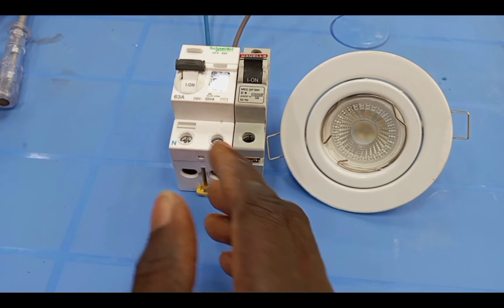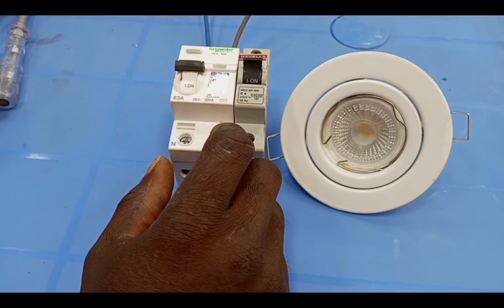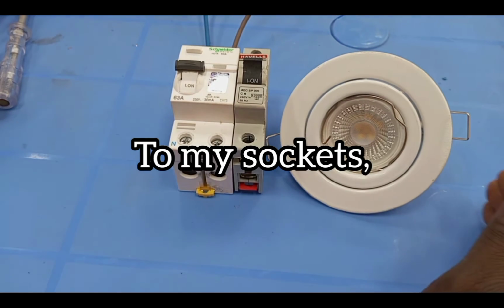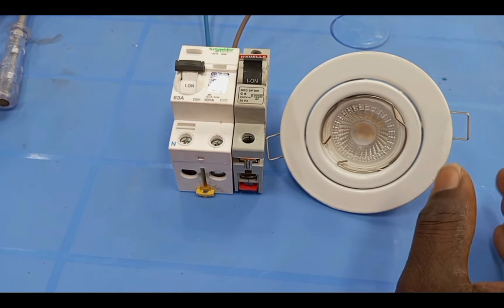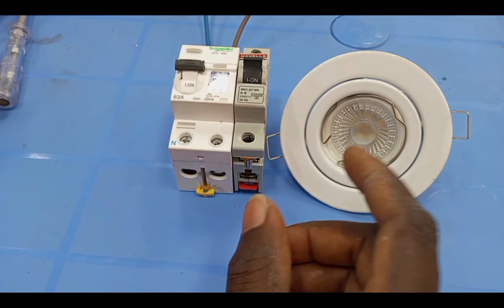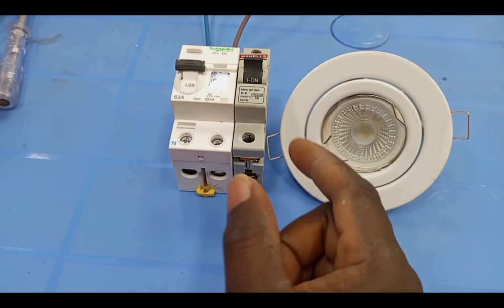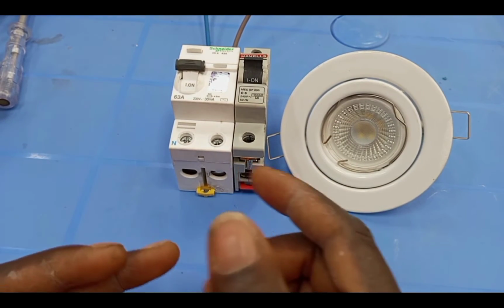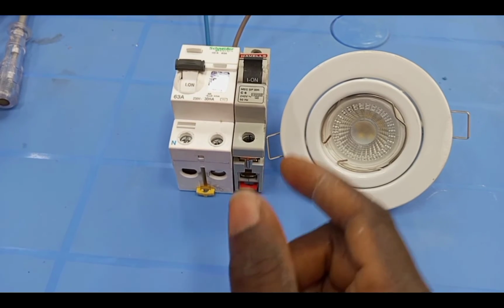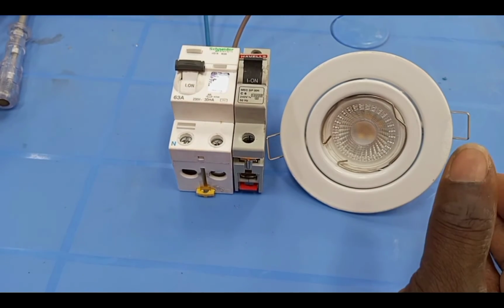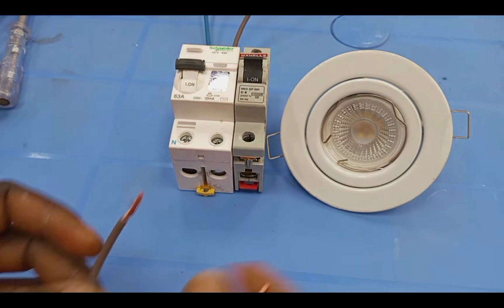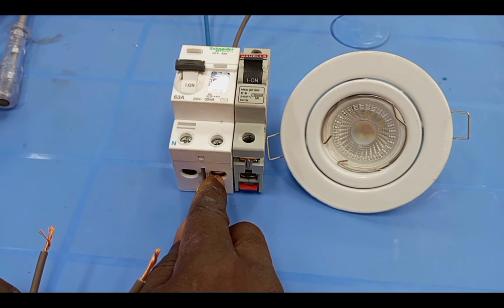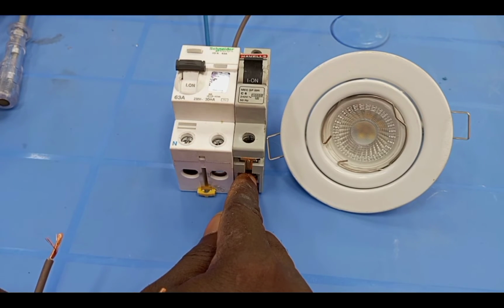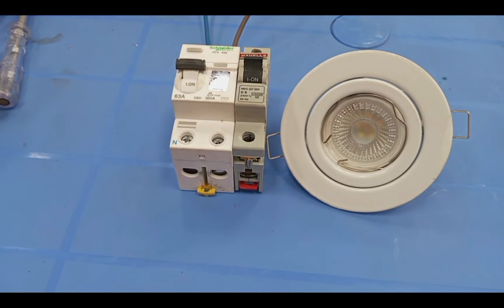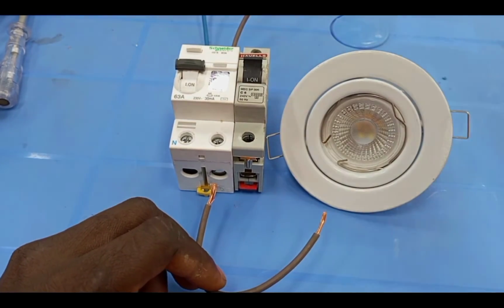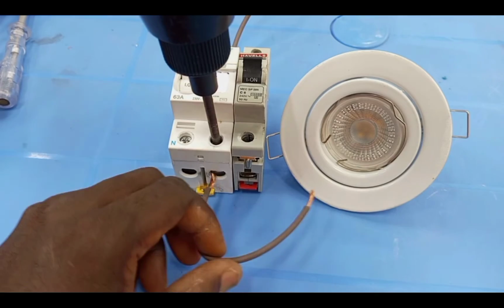In case I want to connect the same RCCB to my sockets, that's my fridge and my televisions and other things, then I will have to use a 16 amp breaker or a 20 amp breaker, depending on the load demand, to protect those ones also. And so this is the live output of the RCCB. So I have to connect it to the MCB that is protecting my lamps. So here we go.